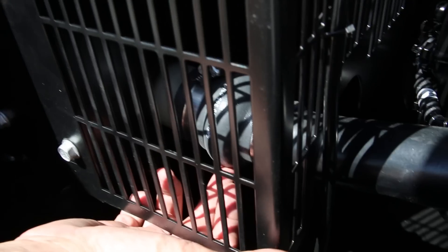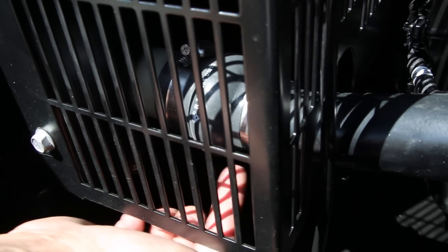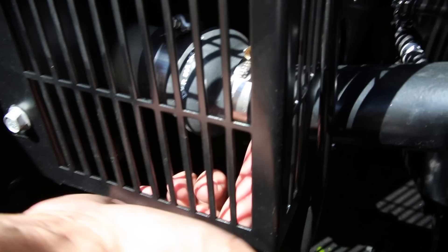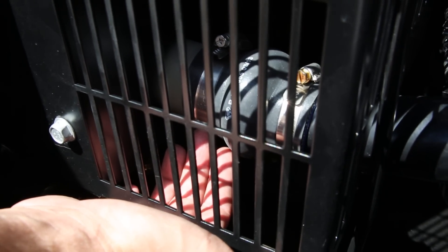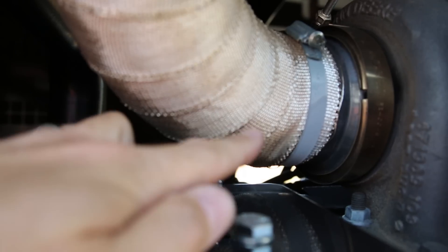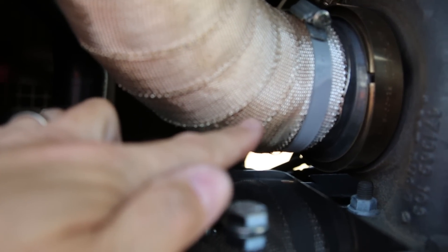Another reason for a generator not pulling full power is loose connections on the intercooler flange or clamps. Check the flange and clamps as indicated, checking the intercooler hose and clamp. Also check the clamp and hose into the turbocharger.